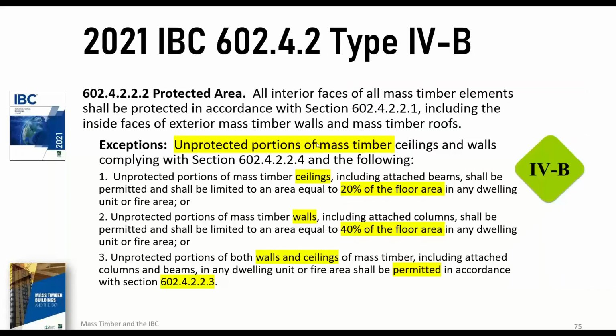So under type 4B, we're going to show you some illustrations of some typical or potential configurations of how to expose the aesthetic qualities of wood underneath those underlying layers of gypsum, non-combustible gypsum protection. So there's configurations to do exposed CLT members on the ceilings and the walls. So when we look at those exceptions, everything has to be protected except unprotected portions of mass timber ceilings, including the attached beams, shall be permitted and shall be limited to an area equal to 20% of the floor area in any dwelling unit or fire area.